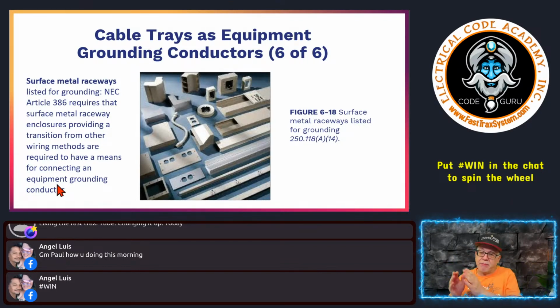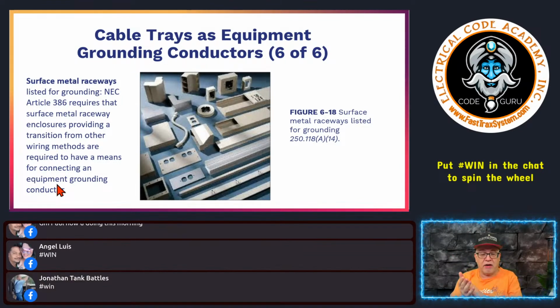But remember, you may see some surface metal raceways where, when the EMT comes into it and connects to it, they may have a lug there. If they have a lug there, then some inspectors may say, well, you know what? I need you to put a bonding bushing and I need you to connect over to that lug with a jumper. If it's all metal, I don't see the need for that.